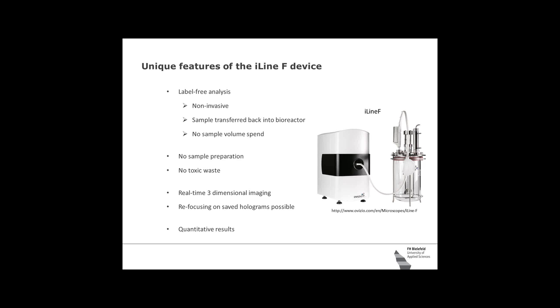This is not the first imaging system, of course, like the CEDEX or the Vi-CELL of Beckman Coulter, the first ones on the market. They also use image data to do the analysis. But when something goes wrong with the autofocus procedure in these systems, you are really in trouble, because you cannot trust the signals anymore, you cannot trust the data anymore, and you have no way to get hold of any information about the process, because the images are not focused, so they cannot be analyzed, and the information is gone.